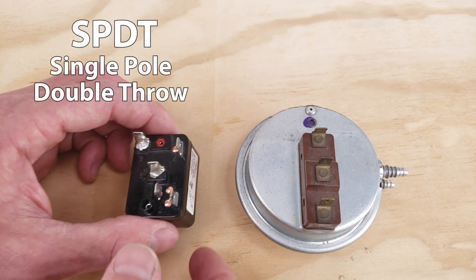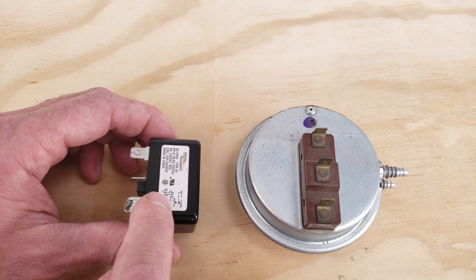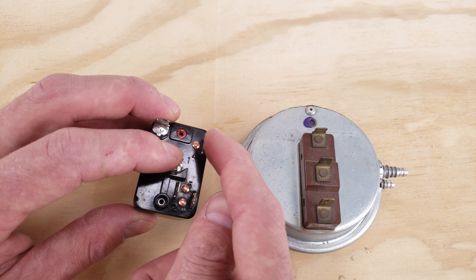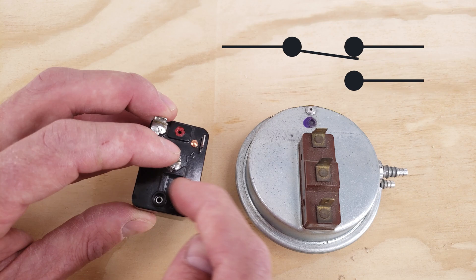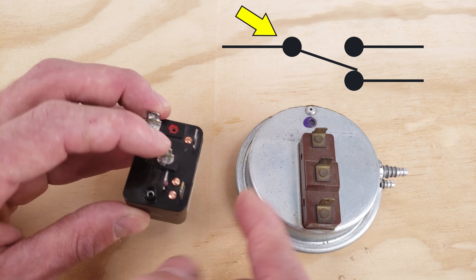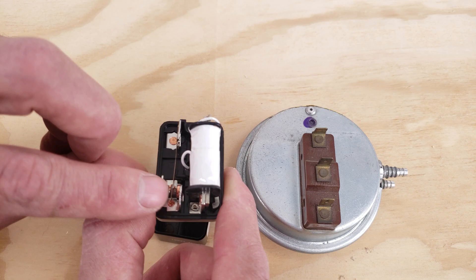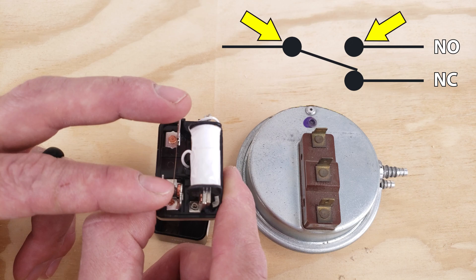Next up you have a single pole double throw switch. In this case we have an 8-amp fan relay and you'd power the coil between one and three in order to activate the switch. The switch would be between 4, 5, and 2, and you have this blade that comes down and switches between these two. It's only a single pole — this is your common connection point and it would throw back and forth between these two contacts down here.